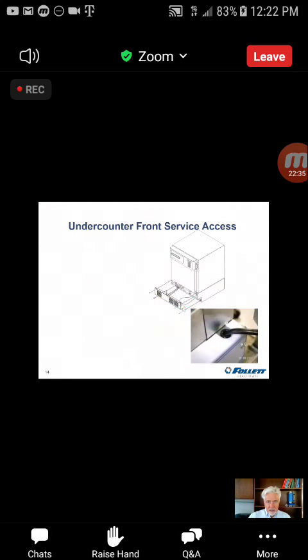Now, on those units, the control board is down here, but the user interface is up here. This is Performance Plus. There is a communication cable that has to go between that control board and the user interface up at the top. So depending on when it was made, there have been some changes here as well. On the original ones, before that serial number, that cable was routed through the front panel. So when you remove the front panel for cleaning the condenser, you have to take care that we don't damage that cable. There is a plastic grommet, and this shows it here a little bit, but this is the new style. There's a plastic grommet that protects the cable, and there's a plastic sheathing that goes over that. So there are 2 layers of protection even before we're talking about the insulation on the wires. When reinstalling that front panel after a condenser cleaning, please make sure that the plastic grommet is in place and that the sheathing has not worked its way down and that we're rubbing bare wire here, because if that happens, it's going to cut the communication cable.